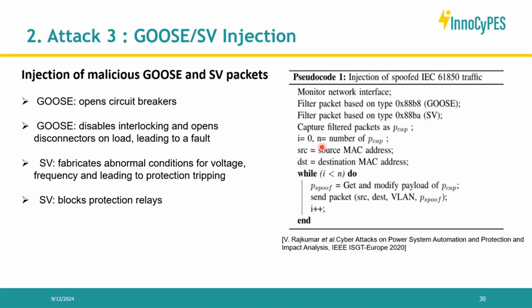For this, you can develop some simple code to use - this was with the help of other colleagues at TU Delft who had already done some work, which we reutilized. You can spoof a packet, meaning you read a real GOOSE packet, and then the attacker uses this real packet, changes it from 'open circuit breaker false' to 'open circuit breaker true', and then injects or replays it back to simulate a GOOSE injection. This is what we mean by a GOOSE injection or sample value injection attack.